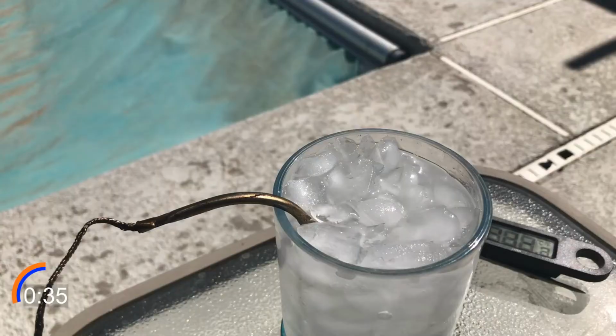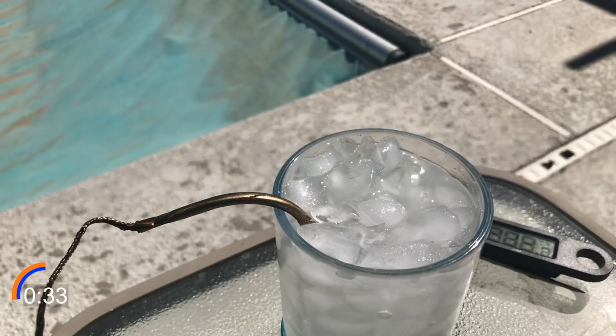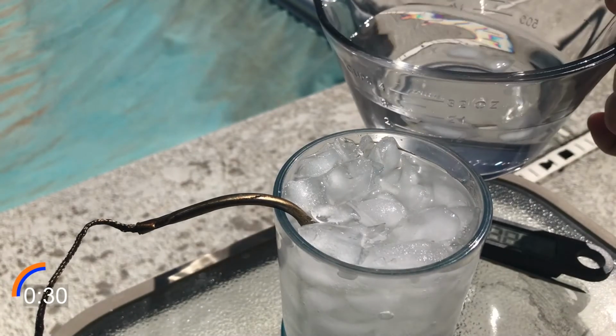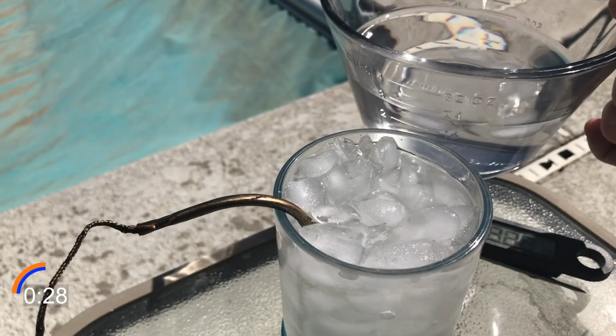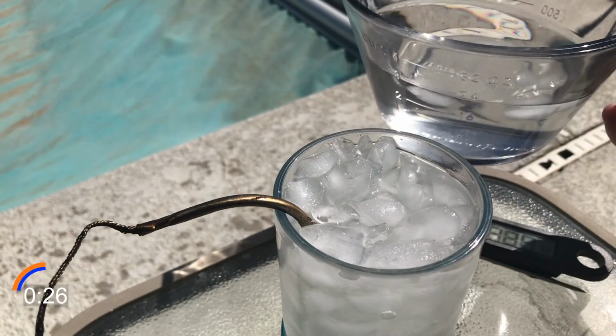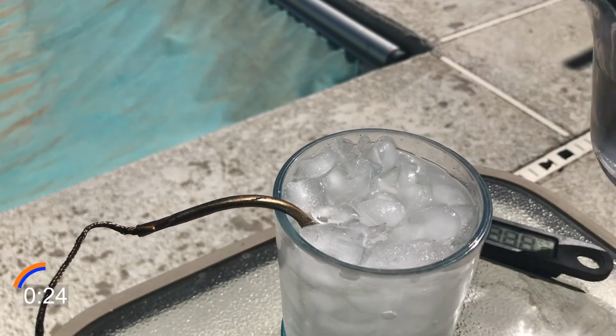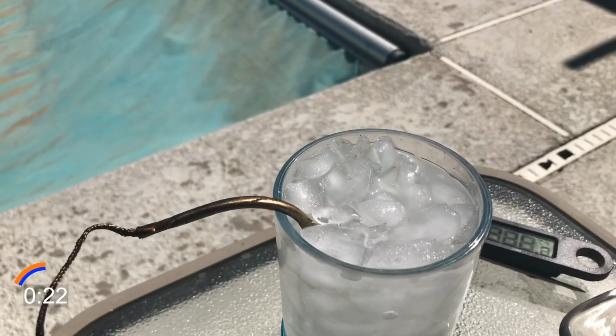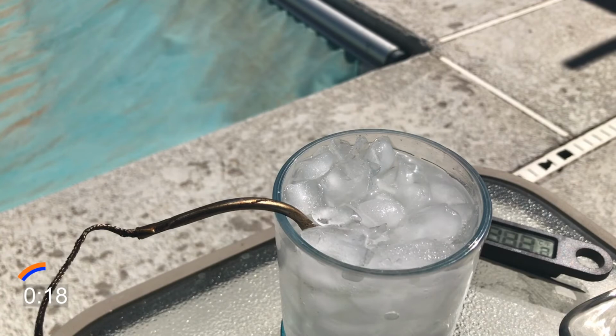Now I want to be explicitly clear that you can't just put it in a little bit of ice water like this, because if you just put it in an ice bath, this is going to read at about 40 degrees or so with just a little bit of ice in there. You want the entire glass packed with crushed ice, and you need to make sure that you have your entire probe submerged.